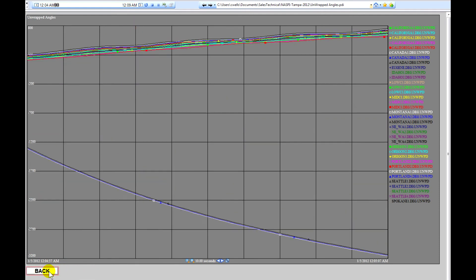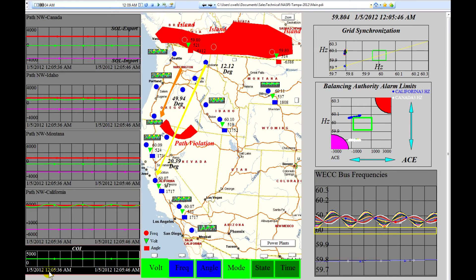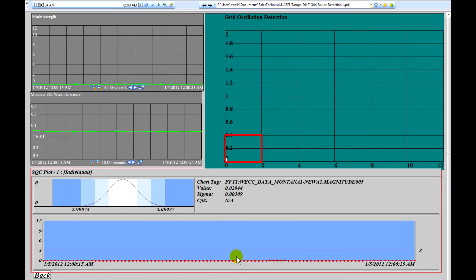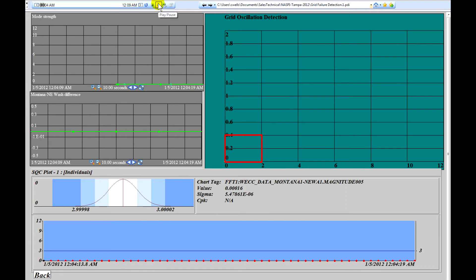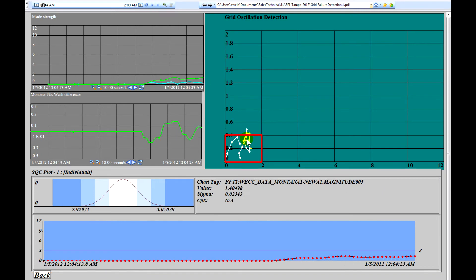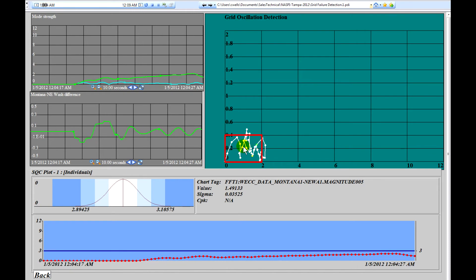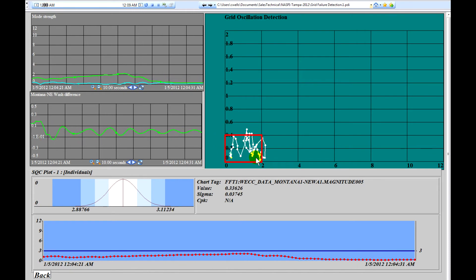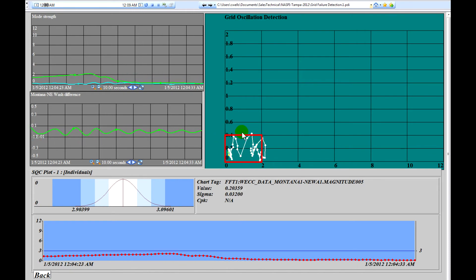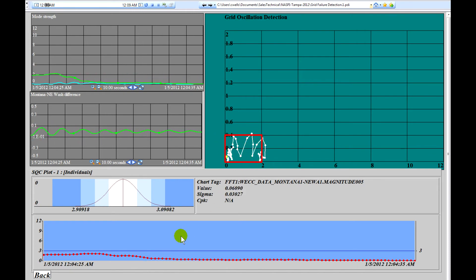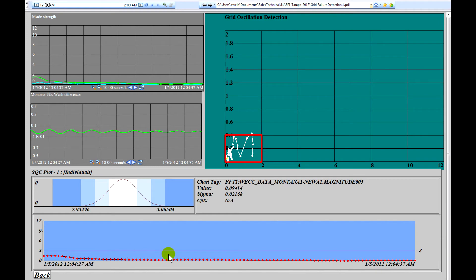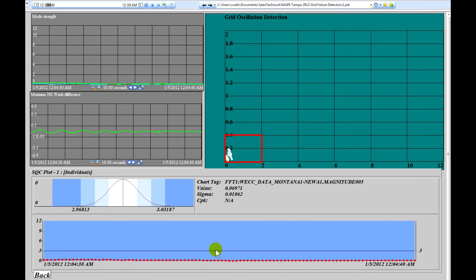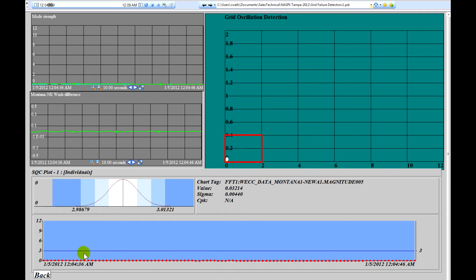We'll go back now to the main page and we'll take a look at the oscillating modes of the system. And we'll see that the system does show some significant oscillation initially, but it's staying within a reasonable set of bounds. And we're below the SQC limit so that it doesn't appear that any oscillation alarms would be triggered.